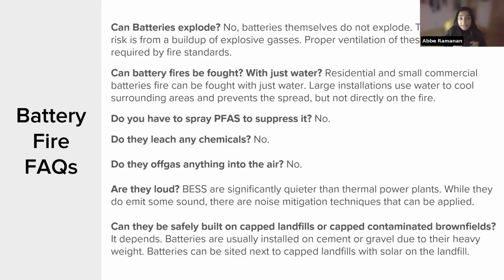Battery storage fires can be fought with water. For larger installations, water is used to cool surrounding areas and prevent spread, but it's not poured directly on the fire itself. You do not need to use any PFAS to suppress it, and leaching chemicals aren't a huge concern. With off-gassing, any gases are very quickly ventilated into the air, so there's not a public health risk there.